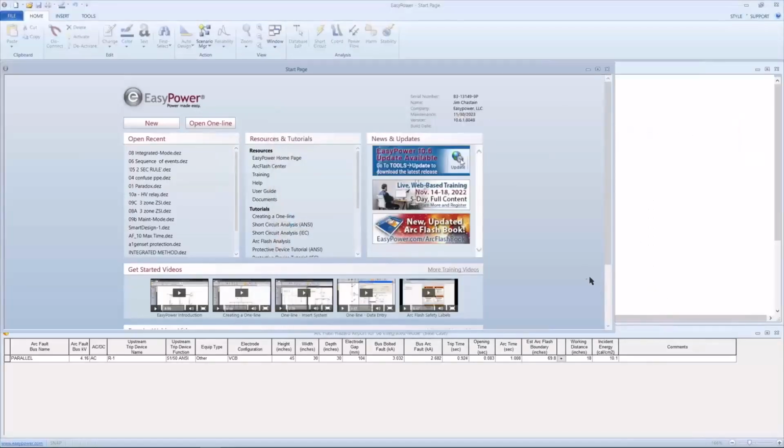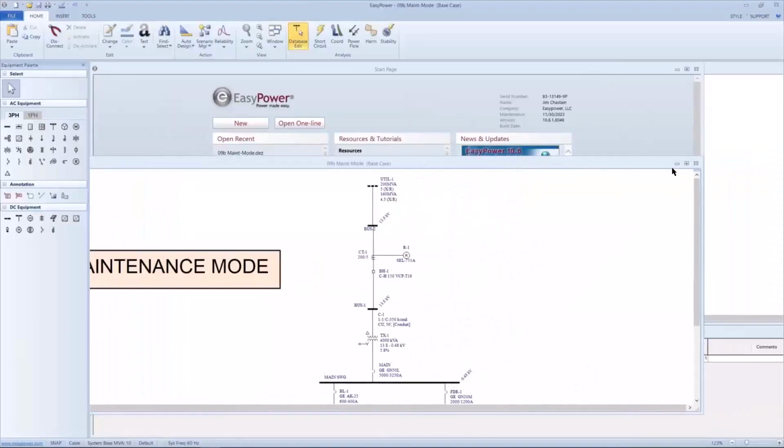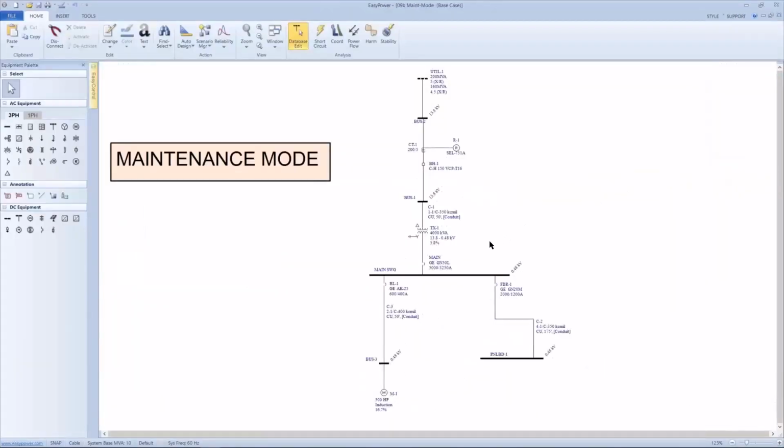is a capability built into, due to modern technology, most low voltage power circuit breakers that lets us control the set points for instantaneous trip based upon either a switch on the front panel of the breaker or on a control line that's controlled somewhere off in the utility room.